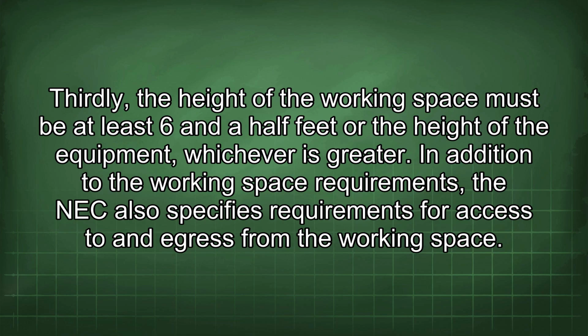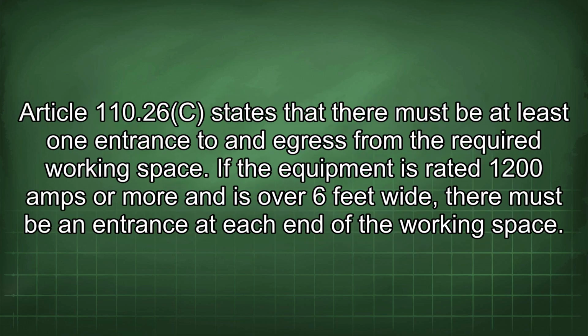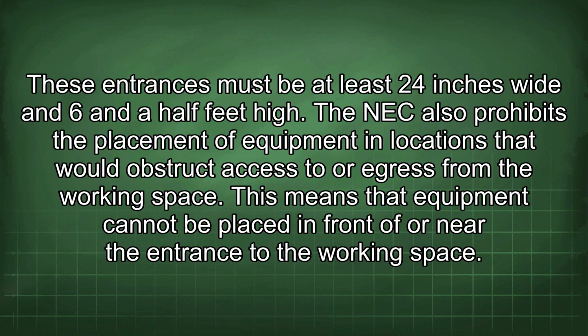In addition to the working space requirements, the NEC also specifies requirements for access to and egress from the working space. Article 110.26(C) states that there must be at least one entrance to and egress from the required working space. If the equipment is rated 1200 amps or more and is over 6 feet wide, there must be an entrance at each end of the working space. These entrances must be at least 24 inches wide and 6.5 feet high.